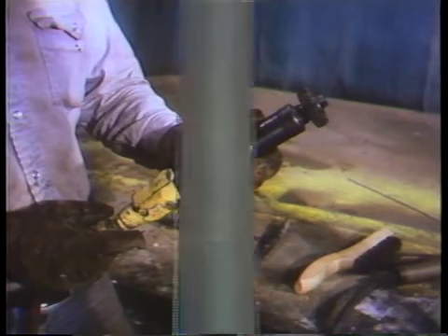There are 5 steps for the repair. Cut out the damaged tube section. Bevel the remaining ends. Cut the replacement tube to size and bevel the ends. Tack weld the replacement section in place, and weld the replacement section to the original tube.